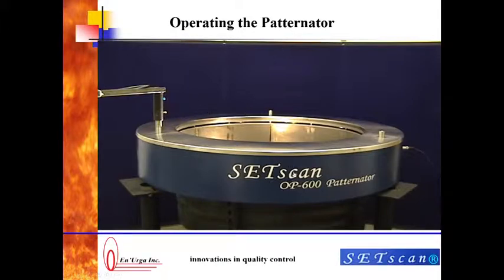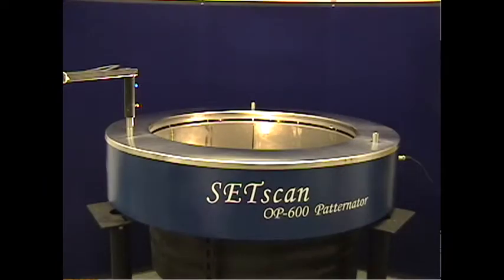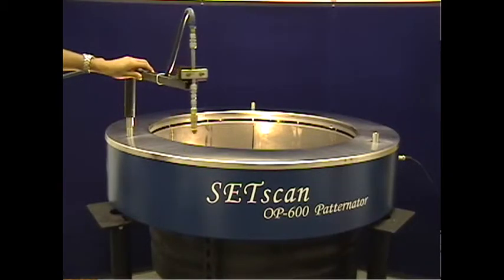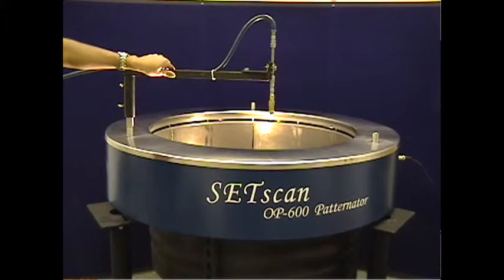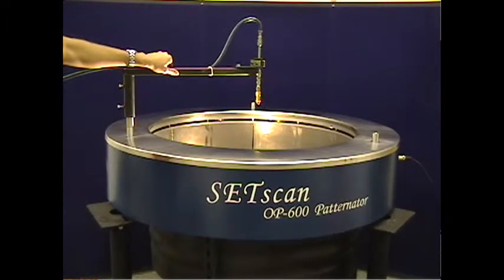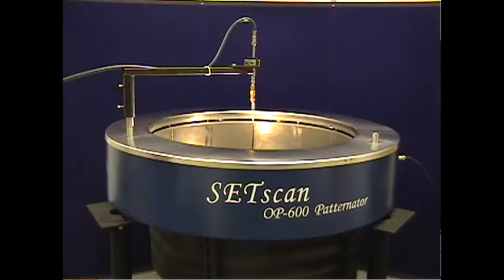Here, the SETScan Patternator can be seen sitting on 3 stands, and what we want to show you is how easy it is to operate this particular patternator. The SETScan patternator has a nozzle that is mounted on a nozzle arm. You move that arm to the center of the patternator and then you start spraying. Once you start spraying, the SETScan patternator collects the extinction caused by the spray at 6 different view angles.